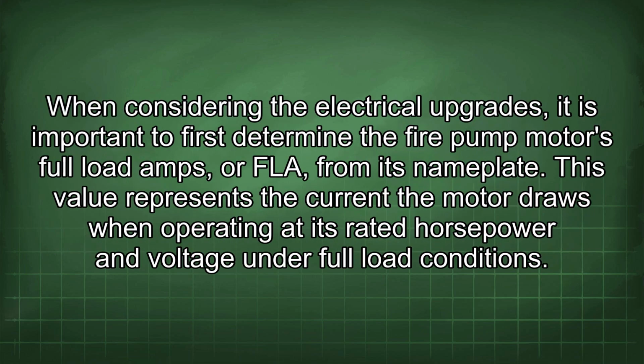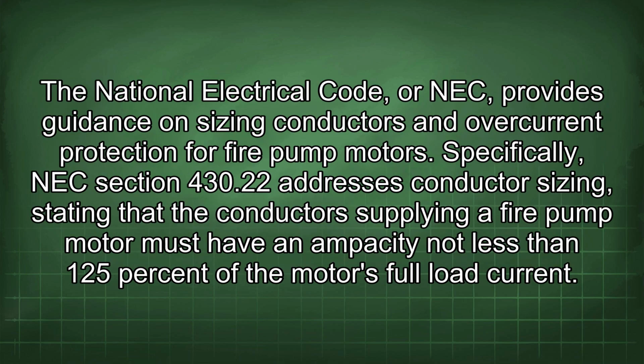When considering the electrical upgrades, it is important to first determine the fire pump motor's full load amps, or FLA, from its nameplate. This value represents the current the motor draws when operating at its rated horsepower and voltage under full load conditions. The National Electrical Code, or NEC, provides guidance on sizing conductors and overcurrent protection for fire pump motors. Specifically, NEC Section 430.22 addresses conductor sizing, stating that the conductors supplying a fire pump motor must have an ampacity not less than 125% of the motor's full load current.